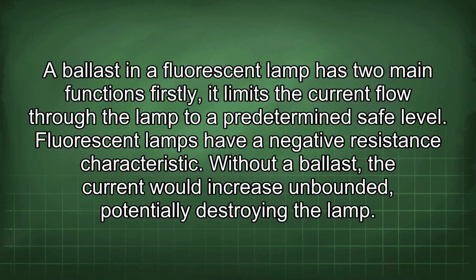A ballast in a fluorescent lamp has two main functions. Firstly, it limits the current flow through the lamp to a predetermined safe level. Fluorescent lamps have a negative resistance characteristic. Without a ballast, the current would increase unbounded, potentially destroying the lamp.